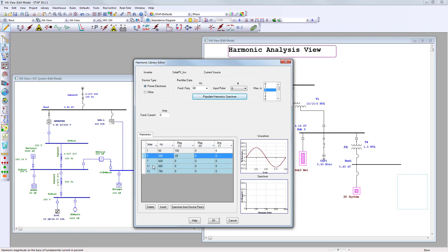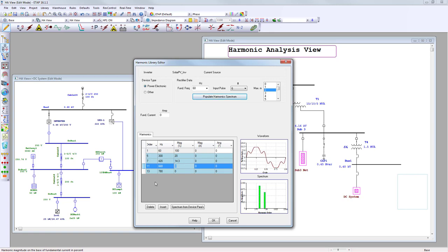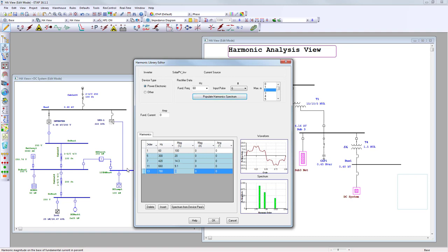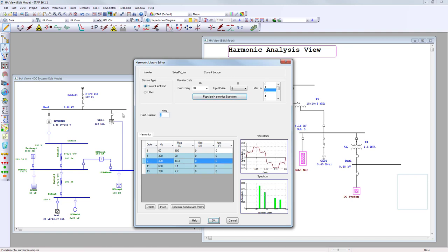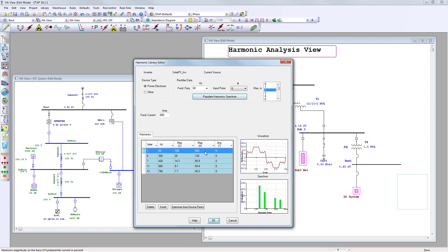For the 5th harmonic, the magnitude is 20% of the fundamental current. For the 7th order it's 14.3%, for the 11th order it's 9.1%, and for the 13th it's 7.7% — taken directly from the data sheet. The fundamental current is 600 amps, and ETAP automatically fills out the magnitude in amps. On the right-hand side you see a representation of the voltage waveform and the current source. Click OK to save.